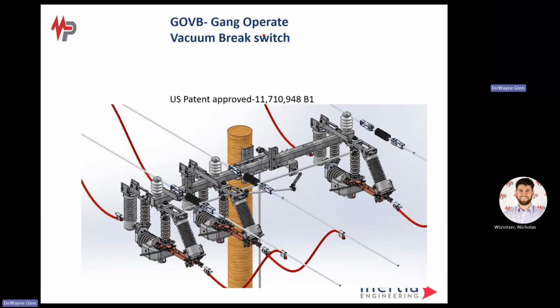Here is something as well. This is a new switch. It's called a vacuum break switch, or group operated vacuum break. We talked about the motor operator with the Schweitzer unit. These are voltage and current sensors on the end of the switch, on both sides of the switch. It kind of looks like long tubes. So they're sensing voltage and current.